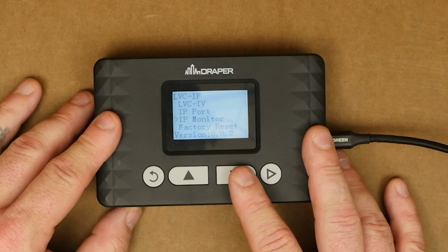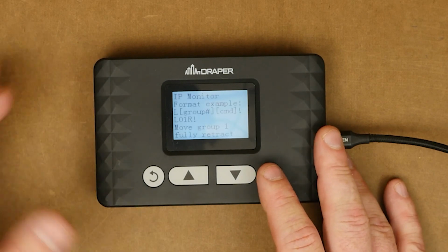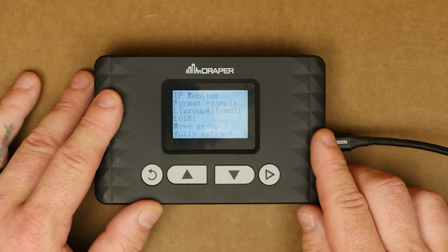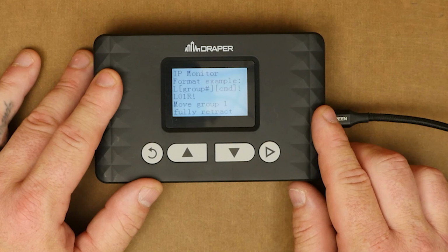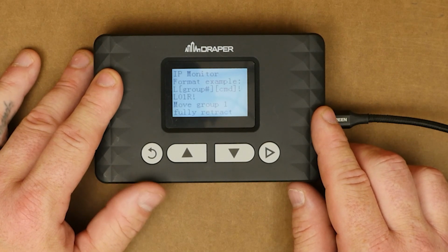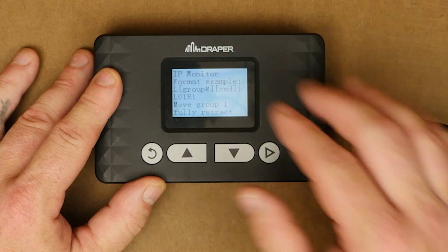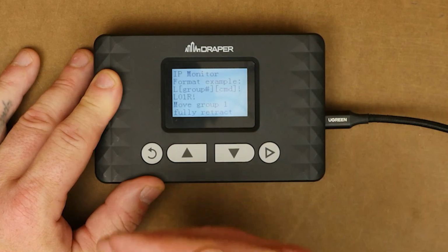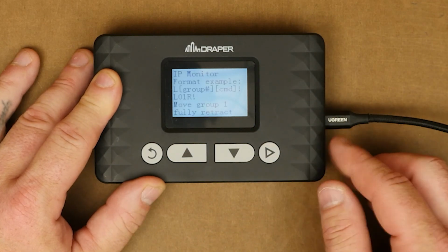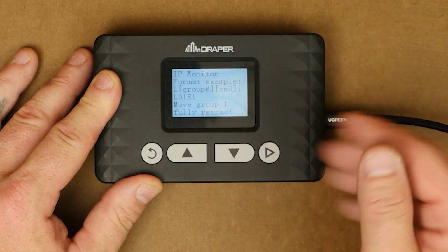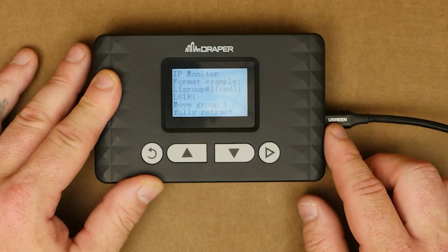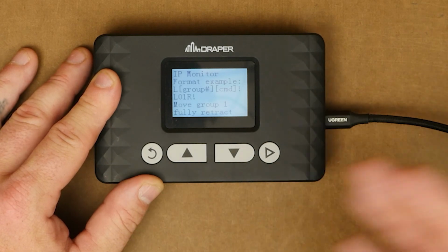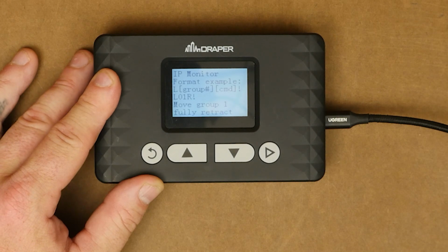Now we are going to the IP monitor port. This is going to be important for initial installation and troubleshooting. What this does is this allows you to see the commands that are being passed along to the LVC IP bridge in real time. So as the integrator is sending commands through, you can monitor it, and it will tell you, hey, we received this command, and it matches this command that we have in our system to move the shades down. You'll see all that right on the screen. However, if they send an incorrect command, you're going to see a bunch of garbage on the screen and it's not going to recognize the command. So it's an instantaneous way to determine if your integrator is using the correct protocol strings or not.